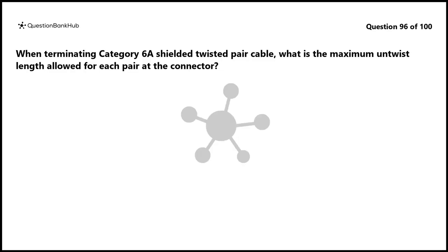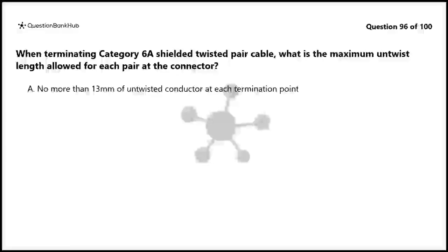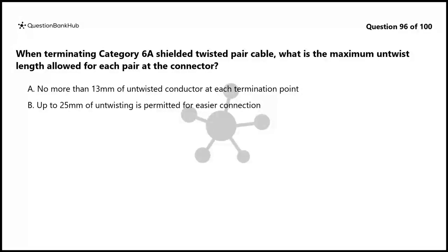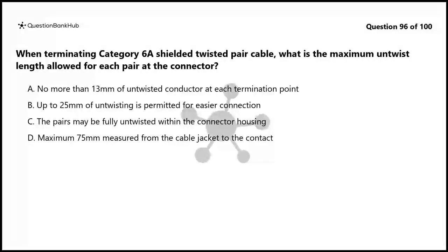Question 96. When terminating Category 6A shielded twisted pair cable, what is the maximum untwist length allowed for each pair at the connector? A. No more than 13 mm of untwisted conductor at each termination point. B. Up to 25 mm of untwisting is permitted for easier connection. C. The pairs may be fully untwisted within the connector housing. D. Maximum 75 mm measured from the cable jacket to the contact.